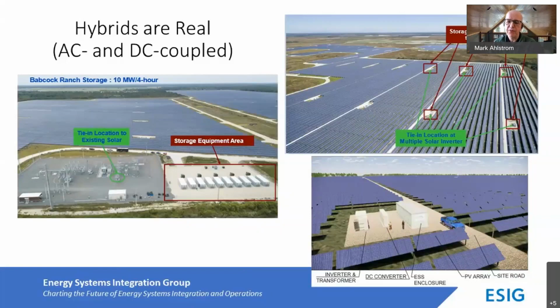With PV plants, typically there's an inverter out with each of the inverter strings, distributed throughout the plant. With a DC design, since you want to share that inverter, you'd put the storage next to the inverter in a more distributed fashion throughout the site. Often there's a DC-to-DC converter too, since the optimal battery voltage differs from the PV voltage — it acts like an inverter in a way but just changes voltage. These have been around for a couple of years now, they're real, they're major projects, and they're working very well, both AC and DC coupled.